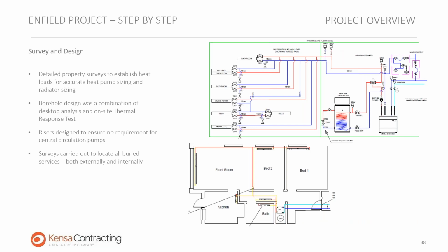Another important part of all of our projects is survey and design. We take detailed property surveys to establish the exact heat loads that are required for that property, and that also gives us a chance to size the heat pump correctly and the radiators as well, because we will be either replacing radiators or fitting new radiators. Radiator sizing is important if you're replacing a gas system, which would typically have 65, 70 plus degree temperatures going through them. We like to run that a lot lower, typically at 45, 50 degrees centigrade. So there may be a slight increase of radiator size. Now that may go from a single panel to a twin panel radiator, but the efficiencies speak for themselves.